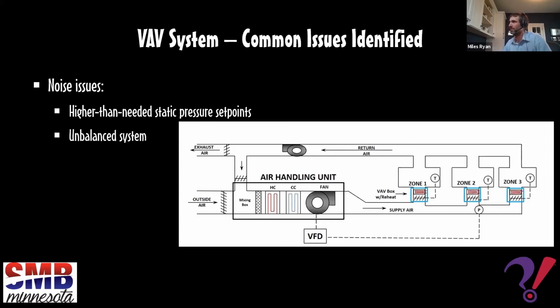Well, with variable speed systems, that's just not the case, because depending on how fast that fan is running, even if that damper is 30% open, if that fan's at 60 hertz or if that fan's at 45 hertz, you don't know what your flow exactly is going through there. So there are more sophisticated ways to control outdoor airflow. One of those would be to install an airflow measuring station in the outdoor air duct, which has its own host of issues that can come out of that.